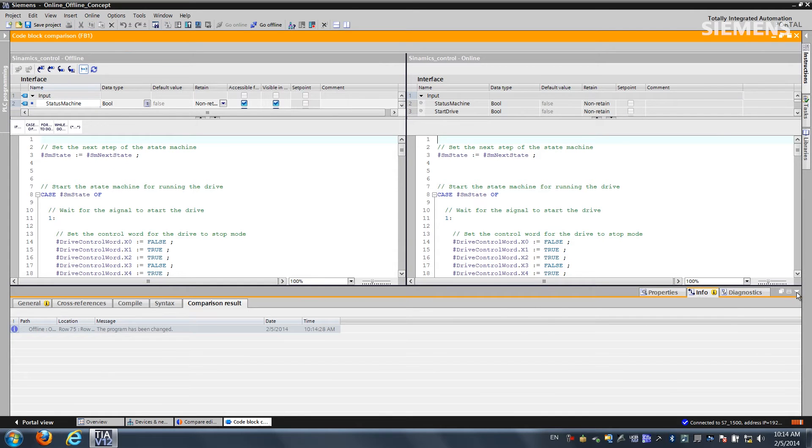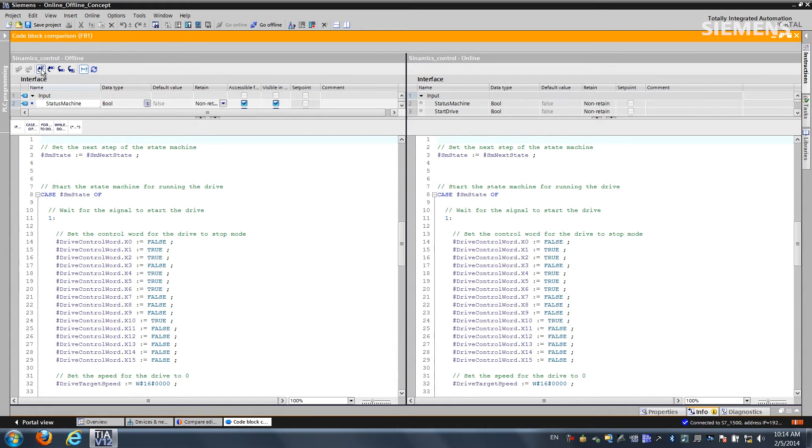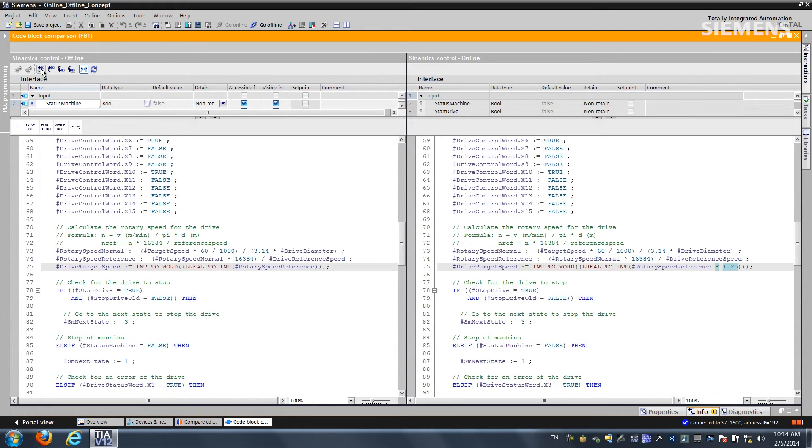As you can see it is SCL code. Now I can use these icons to find the differences. If I use the very first one, he's going to find the first differences in the online offline view. Here it is and I happen to have a multiplication of a 1.25. I know that's not correct because the offline is the actual master.